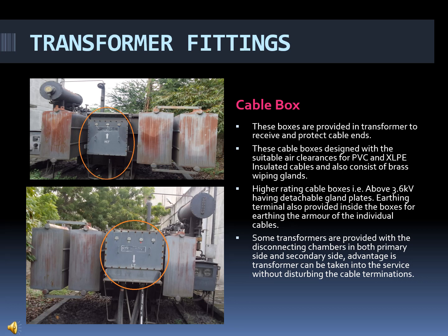Some transformers are provided with disconnecting chambers. In my transformer, the disconnecting chambers have been provided at the primary and secondary side. The advantage of disconnecting chambers is that the transformer can be taken into service or overhauling without disturbing the cable termination. You do not need to take the cable termination out to do the servicing of the transformer. That is the advantage of having a disconnecting chamber at the primary and secondary.